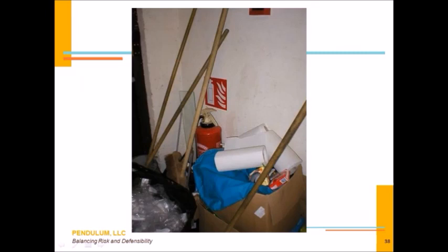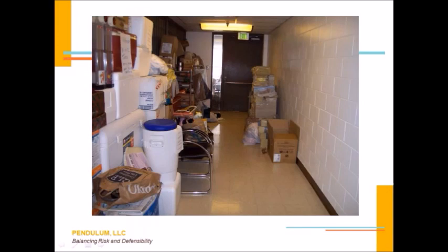When it comes to access to things like fire extinguishers, we see them compromised or blocked all the time. What's the magic number there, everyone? Not 18 inches, it's 36 inches of clear width around those extinguishers, around your pull stations, within the means of egress. We've already talked about reducing the means of egress. This is clearly storage. It can't be only 2 feet or 3 feet on one side. It can't be there at all. Make sure that your corridors are not being used for storage, because the mock surveyor, like me, is going to call you out on it, and the surveyor or the inspector is going to give you the citation, the ticket, or the tag for it.